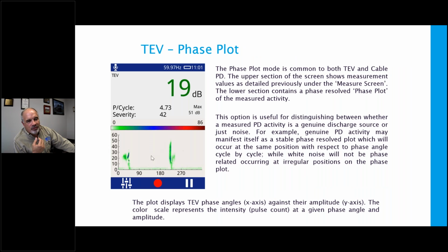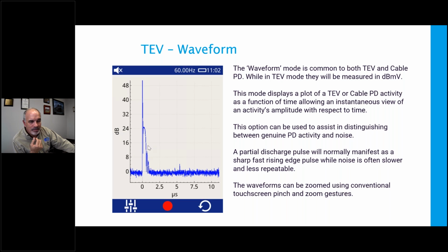You get phase resolve plots from TEV just like you do for ultrasonic, and there's some characteristic plots. This one is not. This is actually off my neon beer sign that I use for creating screenshots. Neon discharge, not partial discharge. But you see we've got 5 pulses per cycle. I'm below my 20 level, so my number's green. And I've got a phase resolve plot. I've got two groupings, but it doesn't look like what I would typically expect. Waveforms. You want to see waveforms that are fast in their rise time, have a little bit of a logarithmic decay to them, and aren't all over the place. So you may have something that's caused by the power system that isn't PD, and the waveform is what's going to tell you the difference.